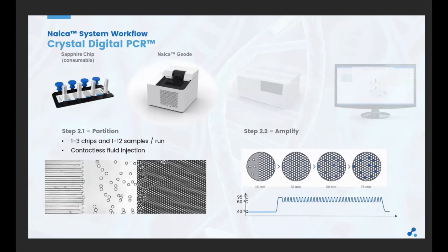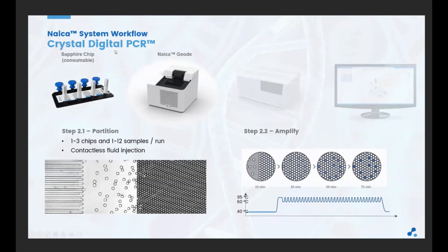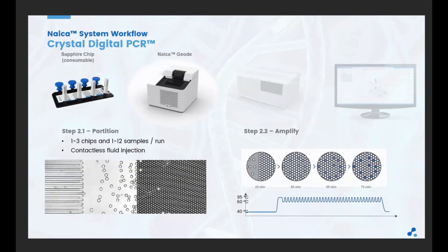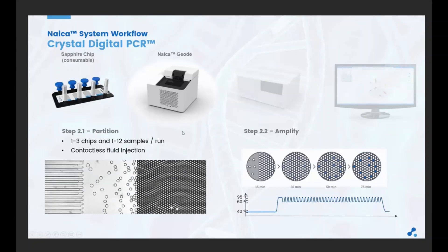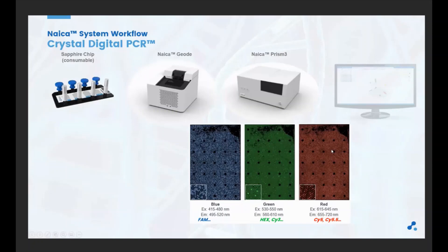Once the sample is loaded into the chips, you place them into the Naica Geode, which can receive up to three chips — meaning up to 12 samples per run. The first step in the geode is an increase of pressure, leading to a contactless fluid injection, pushing the sample through the microfluidics in the chips and generating droplets with a tightly controlled size, as shown in the video. Directly after partitioning, PCR amplification starts within the same instrument. Once amplification is done, the chips are placed in the Prism3 imaging system to read droplet fluorescence in 10 minutes across three channels — blue, green, and red — allowing easy multiplexing of three targets.